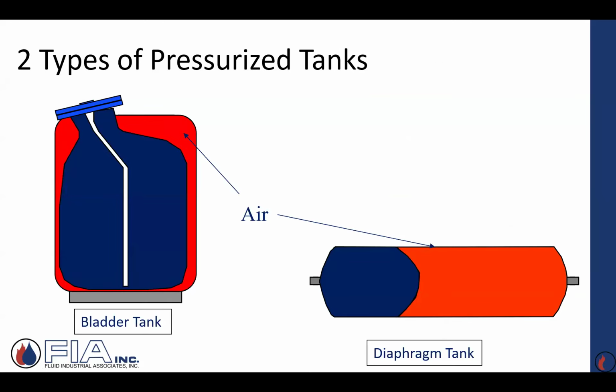And there's just two styles, bladder or diaphragm, two different types. And usually, they achieve the same purpose. One has to do with the smaller systems. The diaphragm is a little less expensive, if you will, in the expansion tank world. So for the smaller hydronic systems, we're going to use diaphragm.